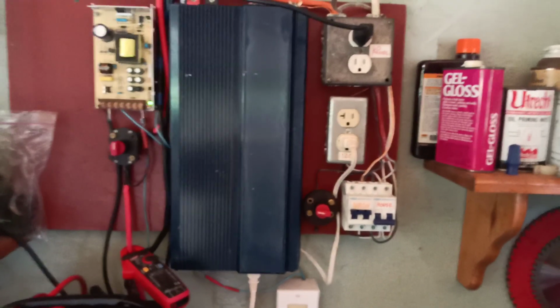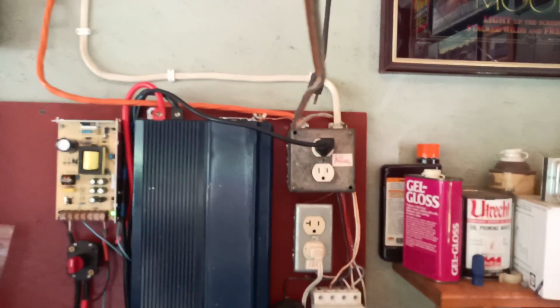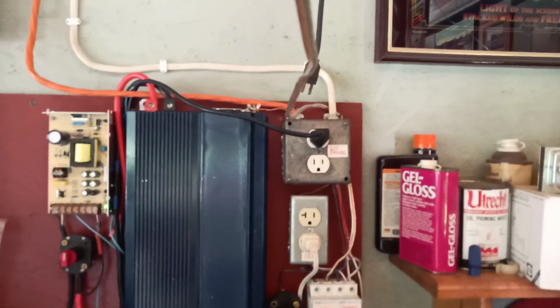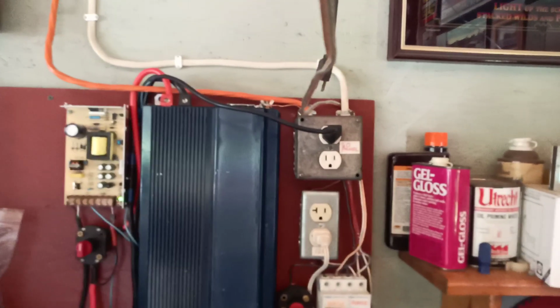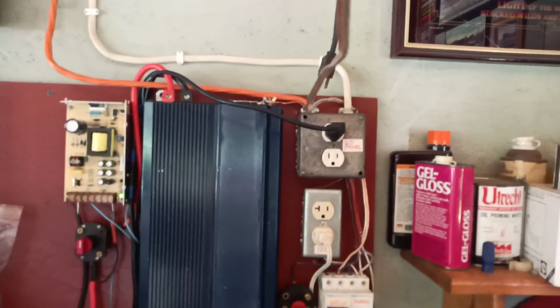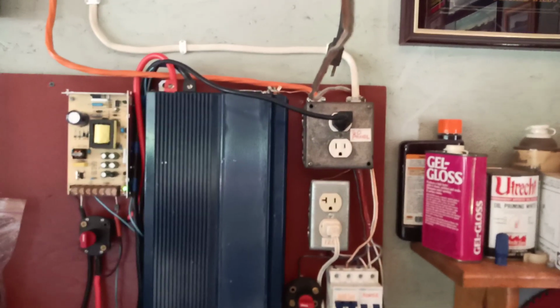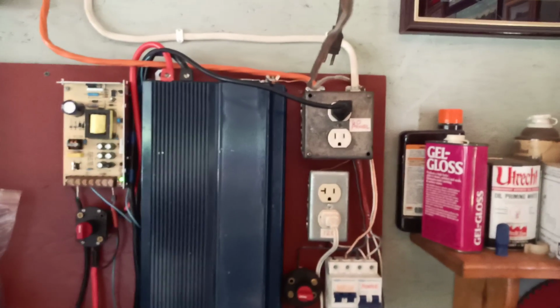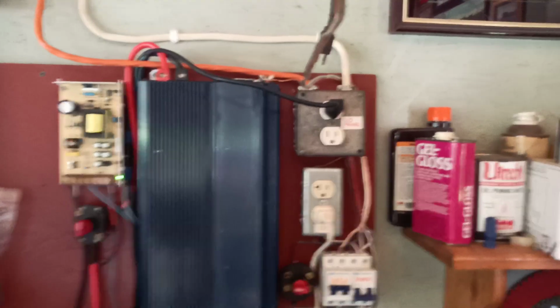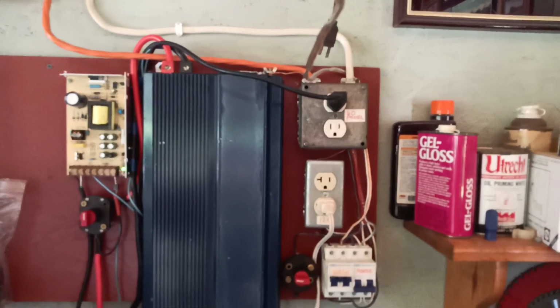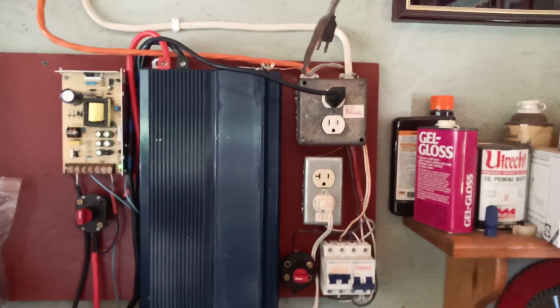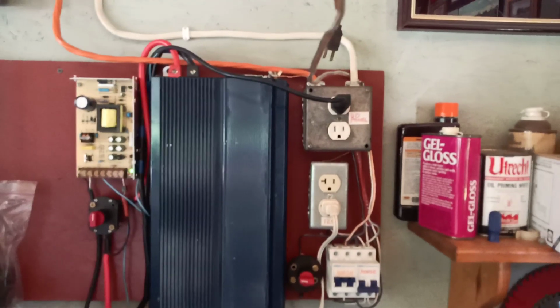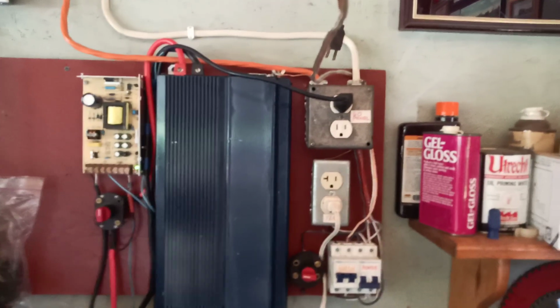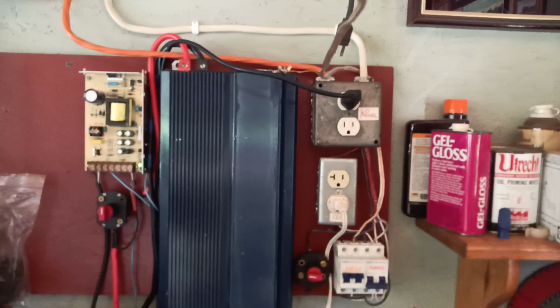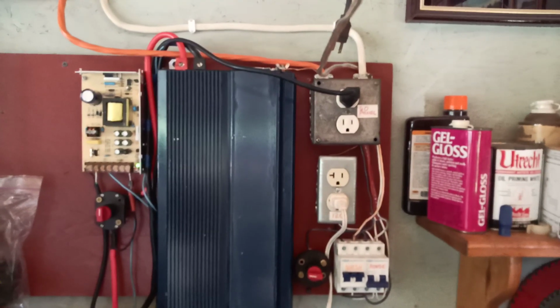And if I put both switches down, this upper outlet box is marked 60 volts. That's what feeds my little trickle charger on the battery. That becomes totally independent. One string of panels can still power the house, but this set of 60 volt string is totally independent, not connected to commons of anything, and that can be used for experimentation.